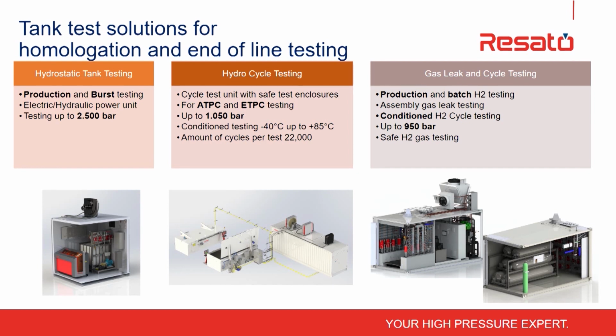We have a scope of supply for the whole test chain for composite vessel testing. One is fluid testing - you need to do a 100% end-of-line test with fluids, done at 1.5 times the working pressure of the pressure vessel, so it can go up to 1050 bar. But you also need to perform a burst test on the tank, and for that we can go up to 2500 bar.